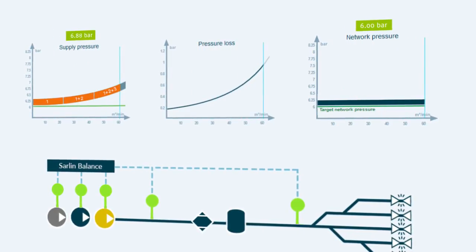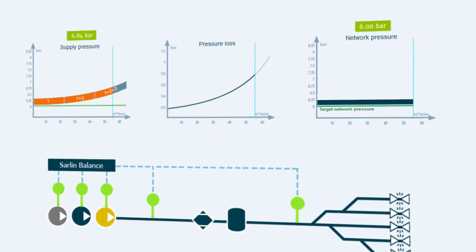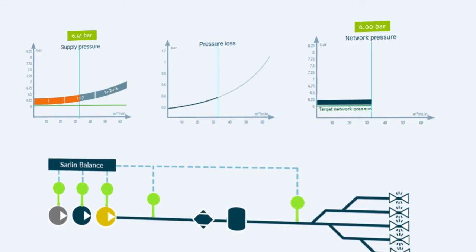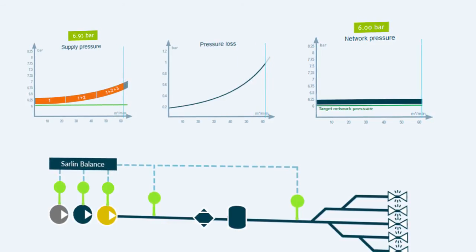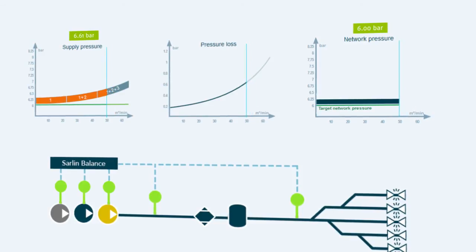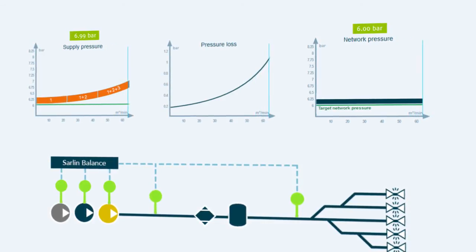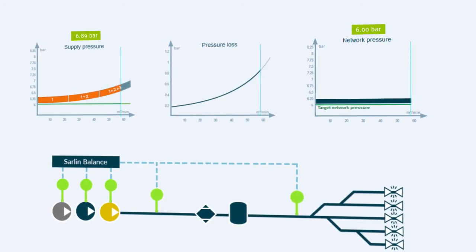Sarlin Balance controls the starting and stopping of the compressors. The output of fixed speed compressors is controlled via load-unload commands. Inverter and turbo compressors are controlled by changing their internal pressure settings. Sarlin Balance keeps the output pressure correct in real time and minimizes the blow-off of turbo compressors.